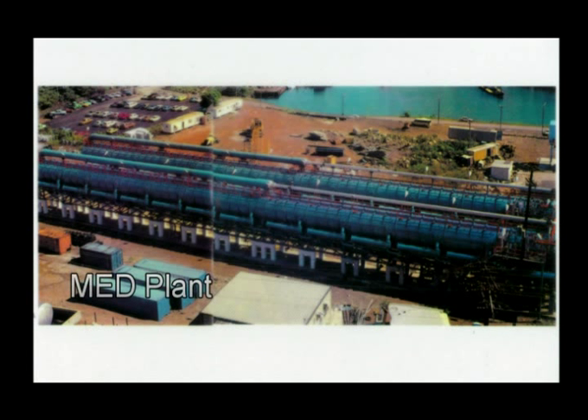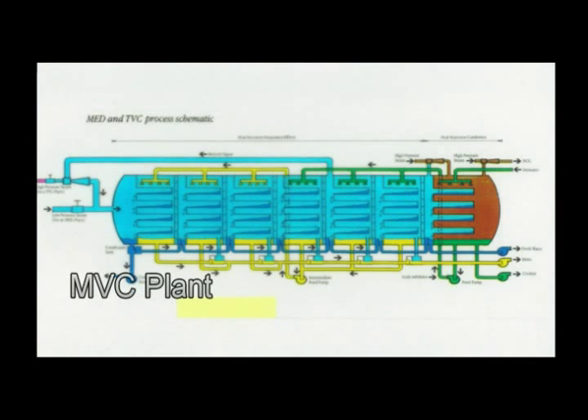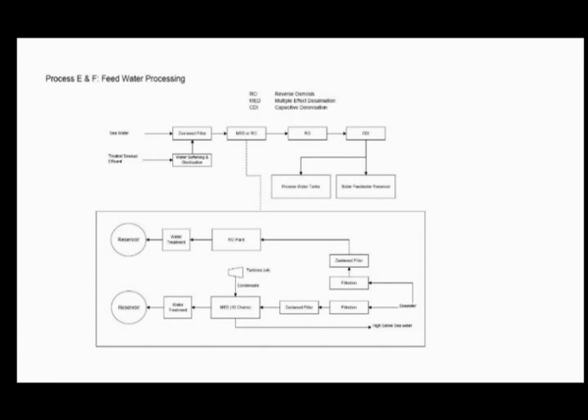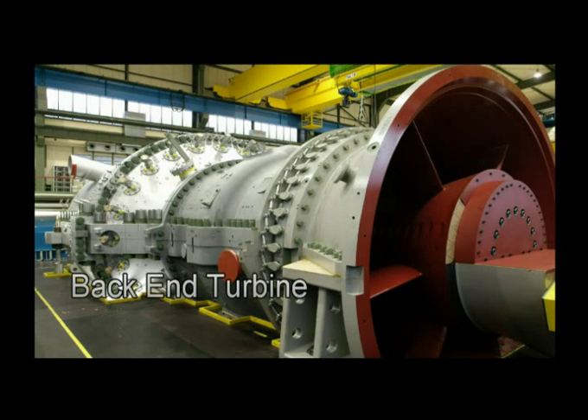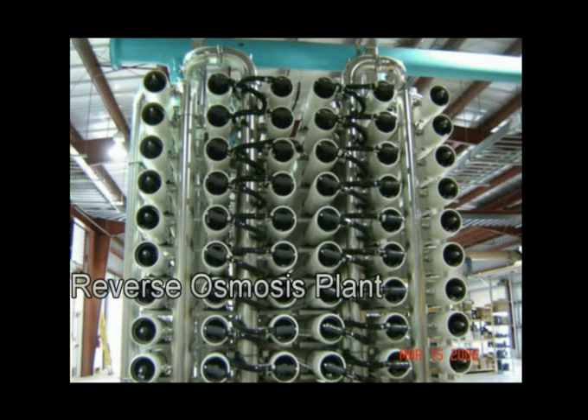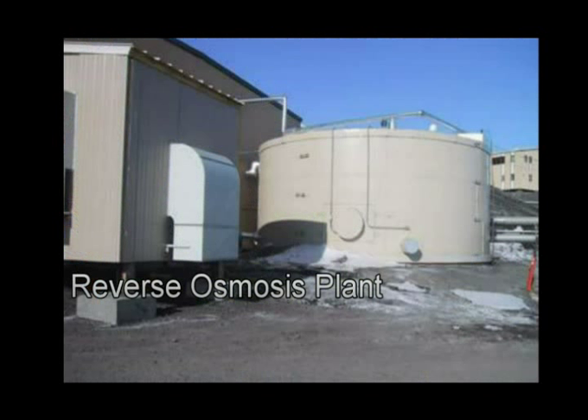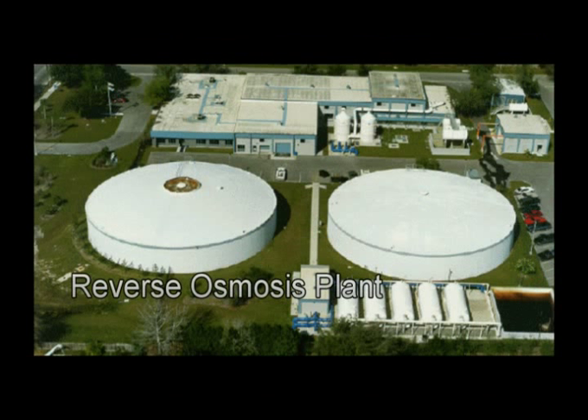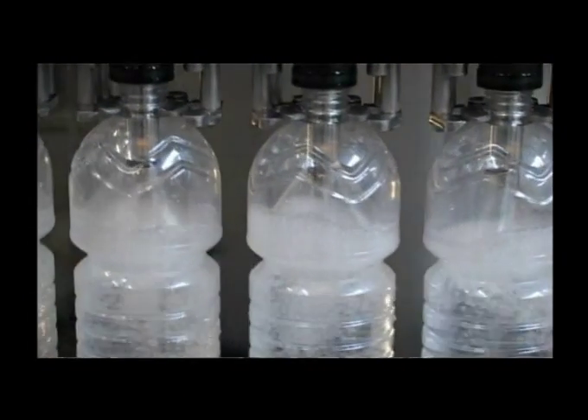In the event of a country choosing to desalinate water, up to 116,000 tonnes of high-quality freshwater per day can be easily produced by multiple-effect desalination in lieu of using cooling towers, with only a small loss of electrical generation from loss of energy at the back-end of the turbine rotor. In water-short areas, a reverse osmosis plant can be used to modulate power export if required. This water is more expensive and has a lesser quality than MED, but when blended and passed through a calcite bed, produces an excellent potable water supply.